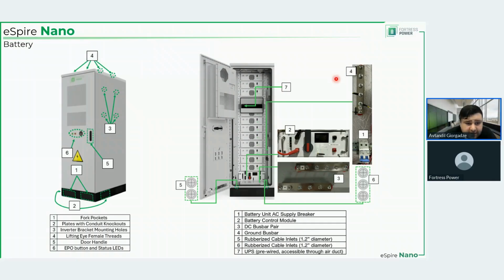Inside the battery, you have, as I said before, the bus bars. That will be number 3, right? You have what we sometimes call the HV box, but in reality, this is the battery management module or battery management unit, however you want to call it. Ground bar, which I showed you before. The AC supply breaker for 480 volt applications to deliver AC to the inverter is also here. And we also have these rubberized inlets.